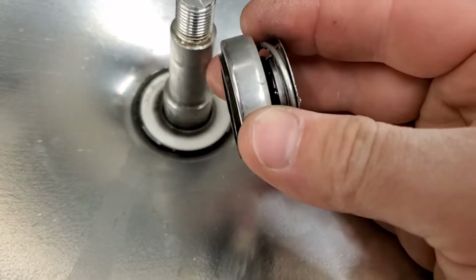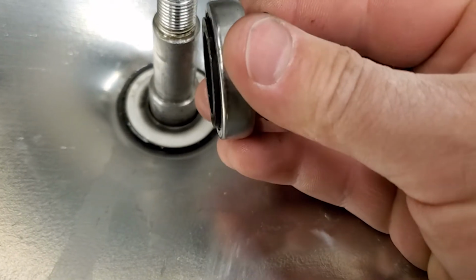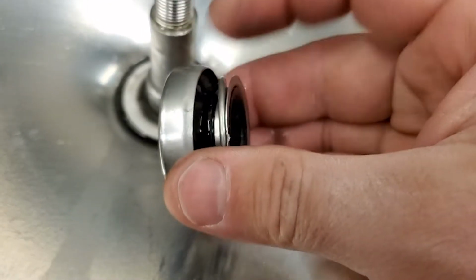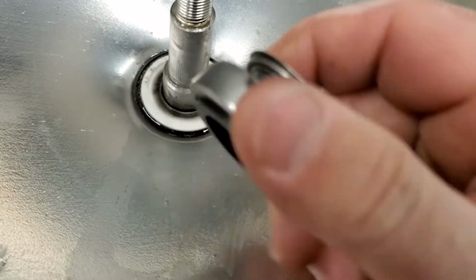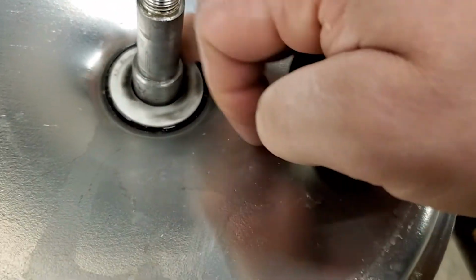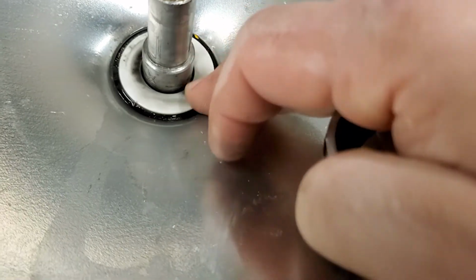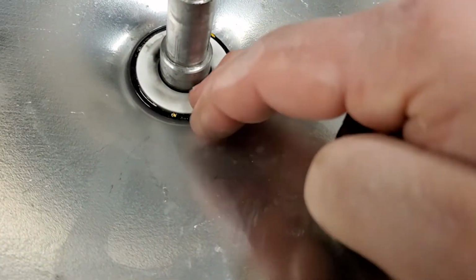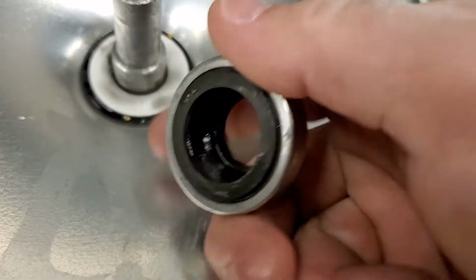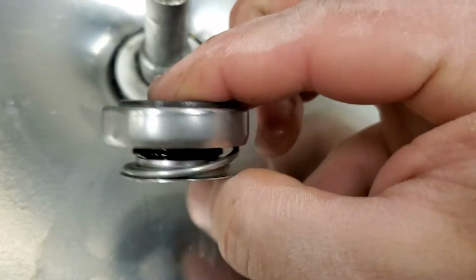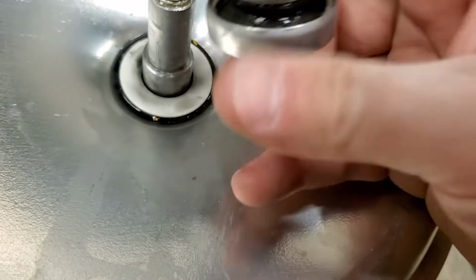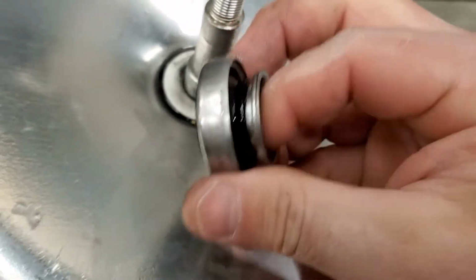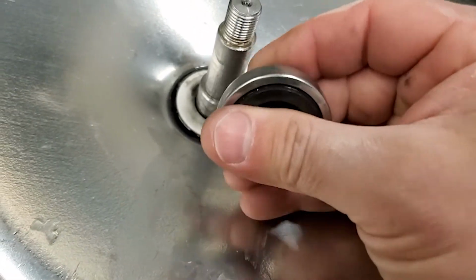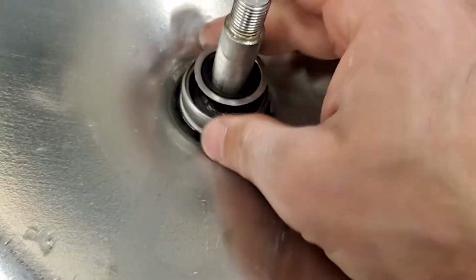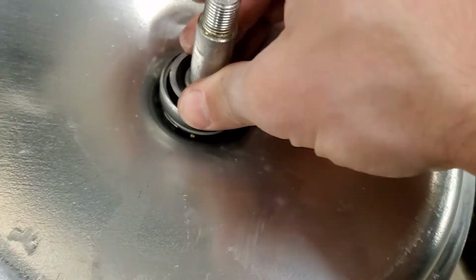So that's another thing you could always listen for, a little squealing at the pump. If it starts squealing, you know you've run out of the carbon on the backside, and you need to probably replace this piece. In that situation, you might actually be able to leave this seal in here, because these seals don't really wear down very often on the backside. It's usually always this piece that wears down, but you can't purchase them separately. They come as a pack, because they want you to change out both to make sure the integrity of the seal system is as good as possible.